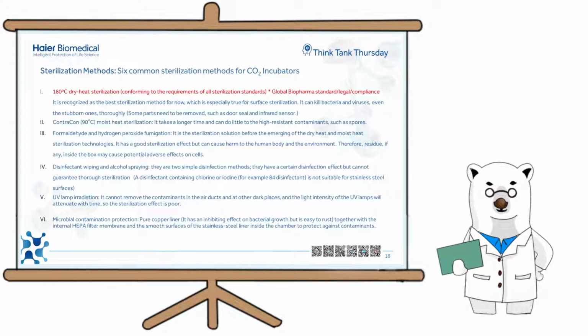Another common one is moist heat decontamination. Moist heat decontamination is often employed on incubators that are not designed to reach the high temperature needed for an effective dry heat sterilization regimen. This may be due to a risk of damage to internal components or the risk of overheating the incubator's outer body.